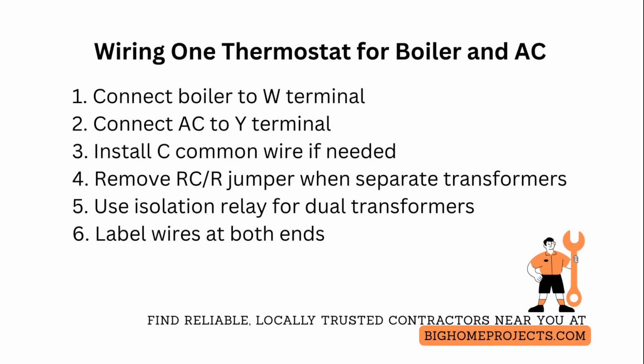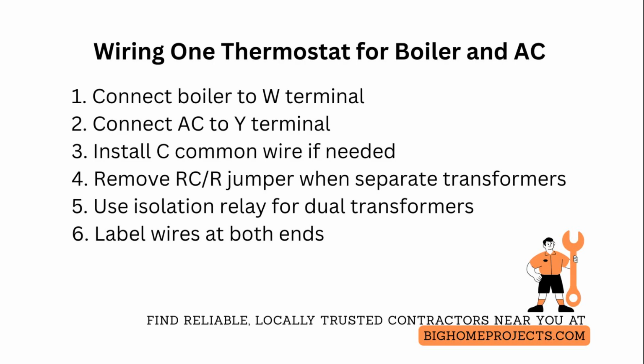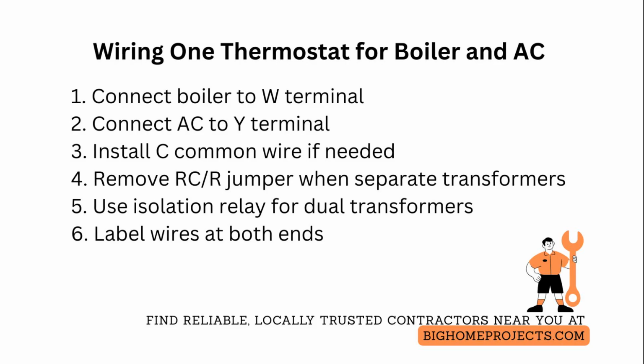Before doing anything, shut off power to the furnace or boiler and the air conditioner at their service switches, and verify voltage with a multimeter. Test for 24 volts between R and C, and verify no continuity between 2 transformer secondaries.